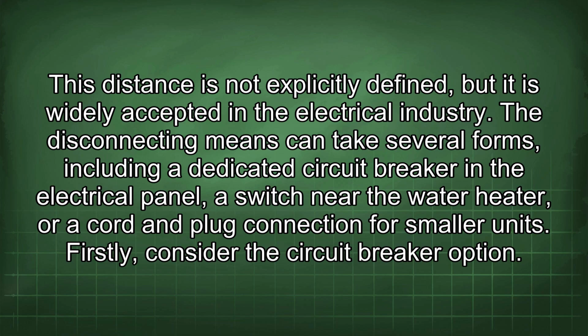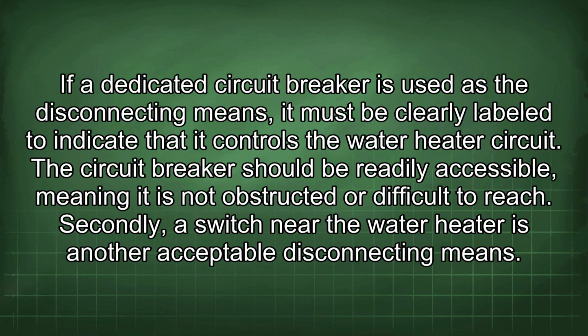Firstly, consider the circuit breaker option. If a dedicated circuit breaker is used as the disconnecting means, it must be clearly labeled to indicate that it controls the water heater circuit. The circuit breaker should be readily accessible, meaning it is not obstructed or difficult to reach.